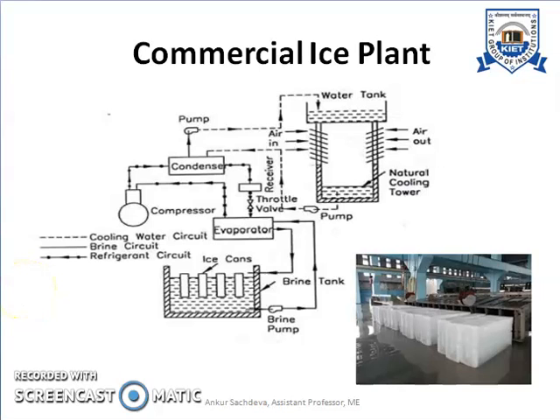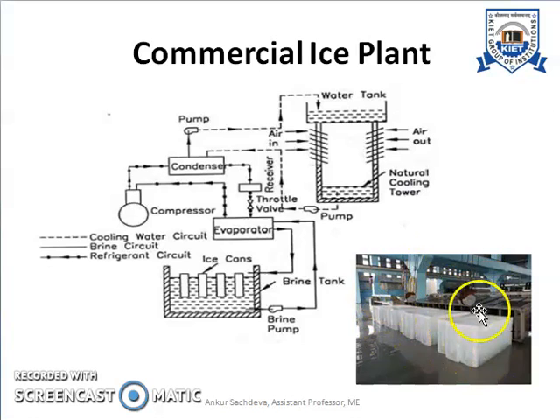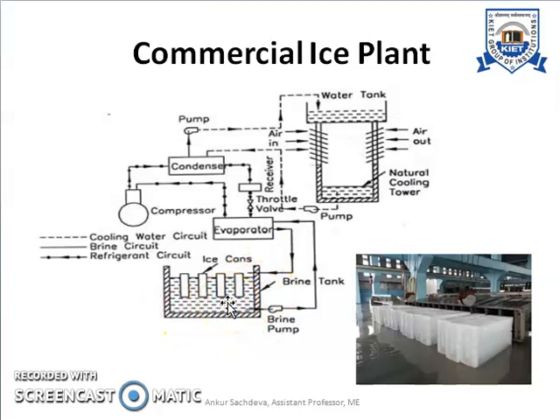Here, as you can see, we have a schematic diagram of the commercial ice plant. At the bottom, we can see a large storage tank where the ice cans are kept. From this ice can, we have the ice in the form of large slabs coming out. As you can see from the picture on the right-hand side, we have large blocks of ice coming outside from the cans. These cans are kept in a large tank inside which we have the brine solution. The level of the brine inside this storage tank is greater than the level of the water kept inside the cans, which contains the potable water required to be converted into ice.